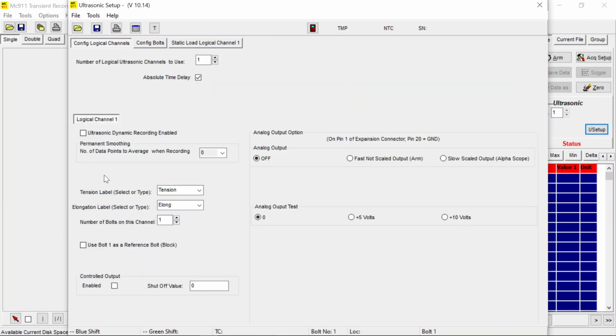If now we want to add the ultrasonic, we go to USetup. So let's start from the top. We have one channel and one bolt. Let's enable the ultrasonic dynamic recording. This would combine ultrasonic with torque angle data. If you do not check this box, then you will not see this information in your recorded data.